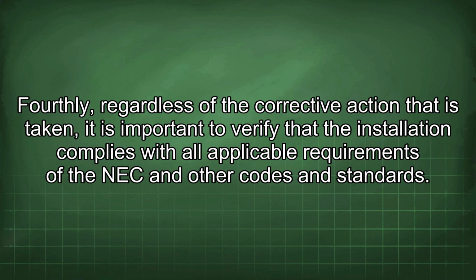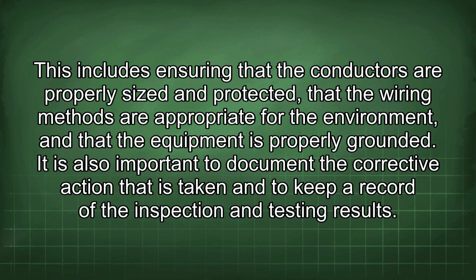Fourthly, regardless of the corrective action that is taken, it is important to verify that the installation complies with all applicable requirements of the NEC and other codes and standards. This includes ensuring that the conductors are properly sized and protected, that the wiring methods are appropriate for the environment, and that the equipment is properly grounded. It is also important to document the corrective action that is taken and to keep a record of the inspection and testing results.